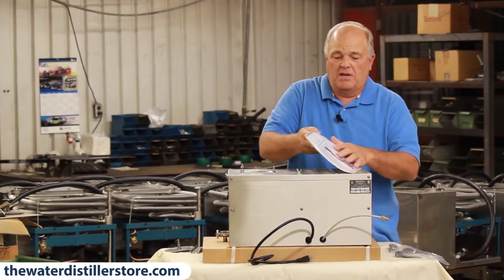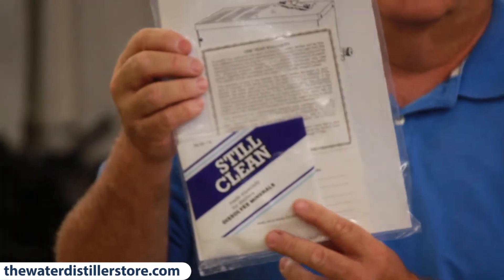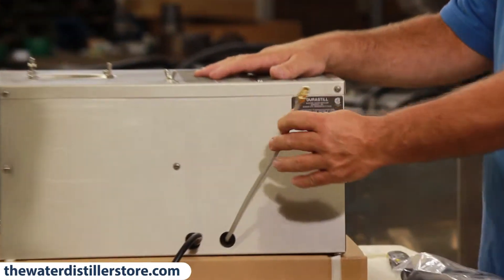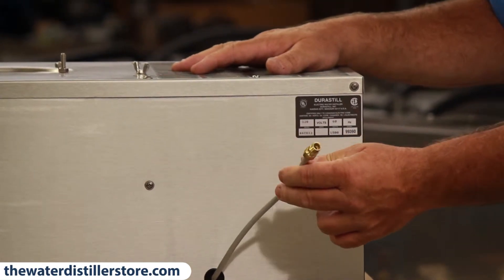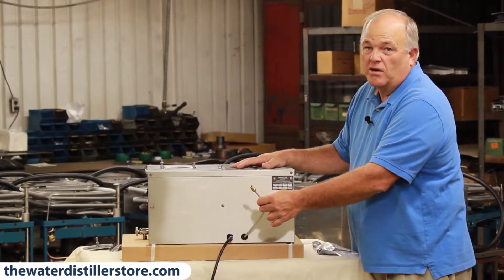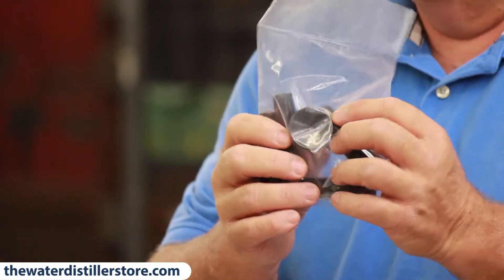When you open it up, you'll have a sample of StillClean, your warranty, and your manual right there in a package. Save that — do not discard it, you'll be needing that. On the back of this distiller is a plug, and since this is an automatic distiller, it also has a water inlet tube right there, just like the back of your refrigerator — it's an eighth-inch OD line that you plumb into your water supply after your pre-filter. There's also a package of legs and a lid knob that comes with this.